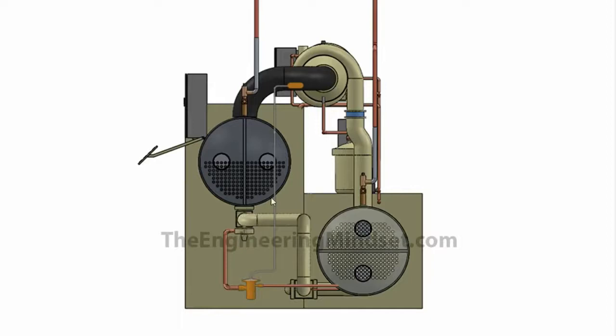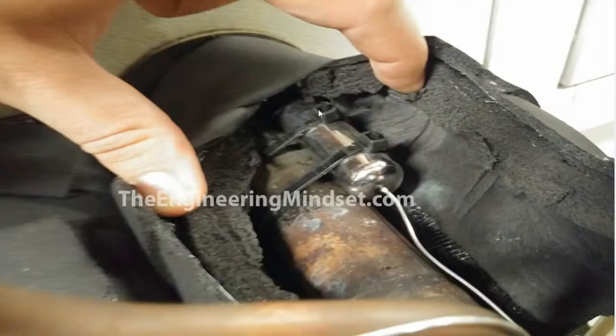We've also got the capillary tube, which rides up here into the thermal bulb, which is attached to the suction line just before the compressor. And then the main refrigerant flow will pass through here, through this pipe, into the main valve. This expansion valve decides if it's allowed to pass or not, and if it is, then the refrigerant will flow into the evaporator. So the thermal bulb will be located on the suction line, and it looks a bit like this, with the capillary tube running along here.